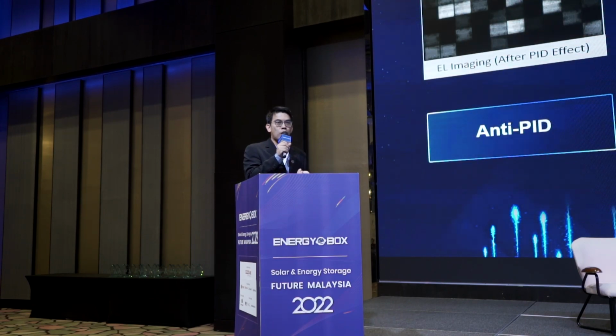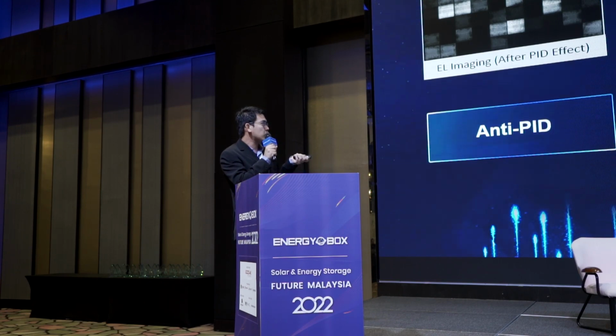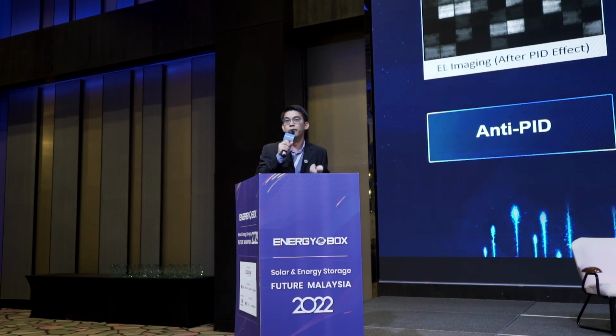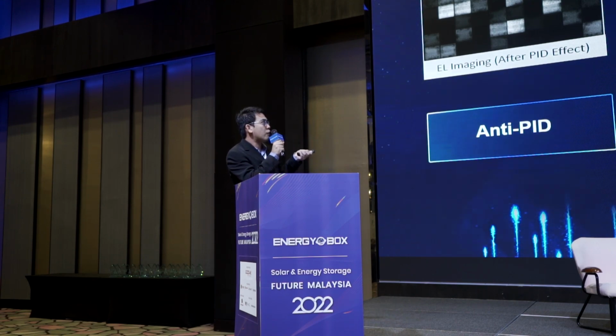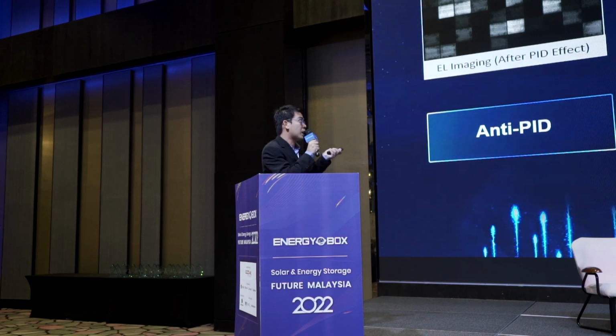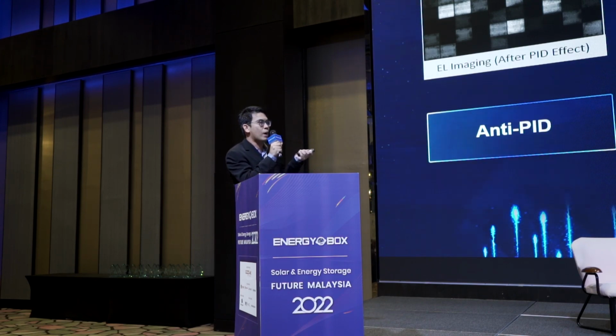And of course, at the same time, we also have a full solution for PID. We have both solutions. One we call Anti-PID, and the other one is PID recovery. The Anti-PID device would work all the time, be it daytime or nighttime. It will make sure that the minus voltage to ground of the PV panel string is always above zero. This is extremely important if clients are using thin film modules, where they have a very concrete requirement that the module needs to always be above 0 volt. And of course, we also have PID repair solutions, which are more suitable for monocrystalline products, where you only work during the nighttime when the inverter is not working.